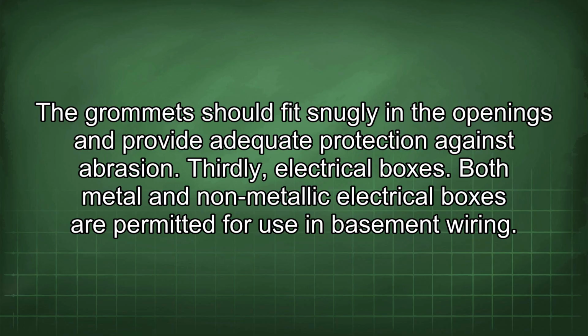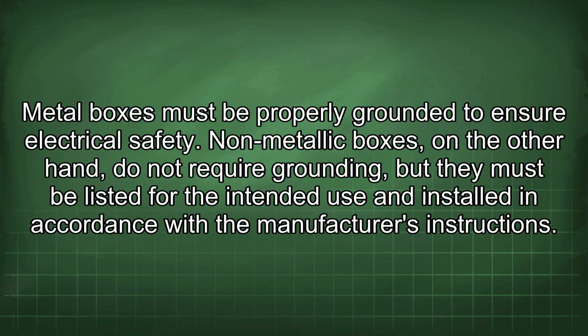Thirdly, electrical boxes. Both metal and non-metallic electrical boxes are permitted for use in basement wiring. Metal boxes must be properly grounded to ensure electrical safety. Non-metallic boxes, on the other hand, do not require grounding, but they must be listed for the intended use and installed in accordance with the manufacturer's instructions.